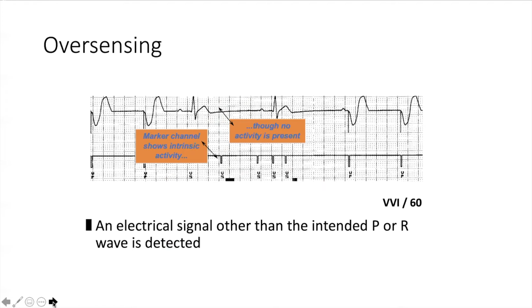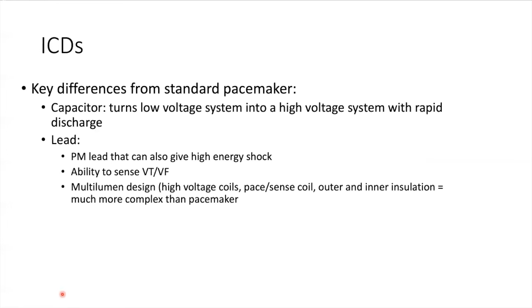How are ICDs and pacemakers different? The key difference is ICDs need a lot more power to deliver high energy therapies. So they have a capacitor, which can turn a low voltage system into a high voltage system with rapid discharge. The lead is essentially a special pacemaker lead that can pace, sense, but it can also give a high energy shock and sense VT or VF. These are generally more complex leads than you see in a pacemaker. They've got a multi-lumen design with high voltage coils, a pace sense coil with outer and inner insulation. So these are much more complex than a pacemaker.